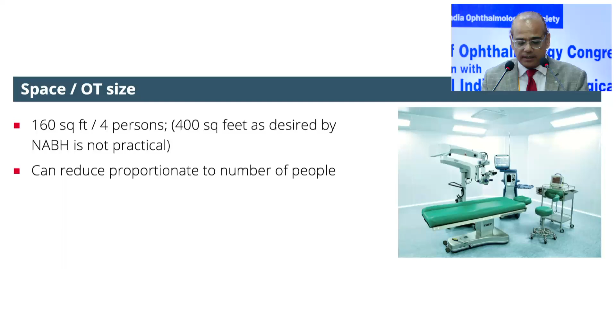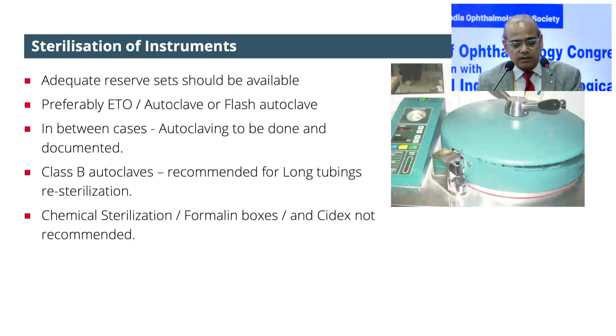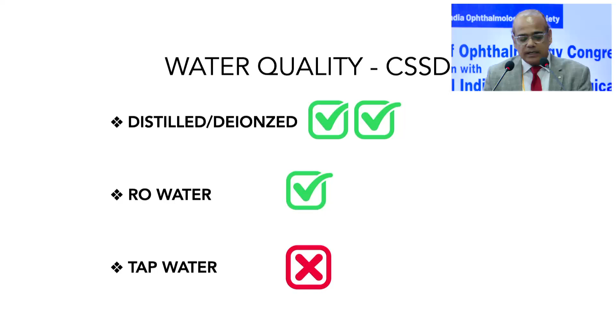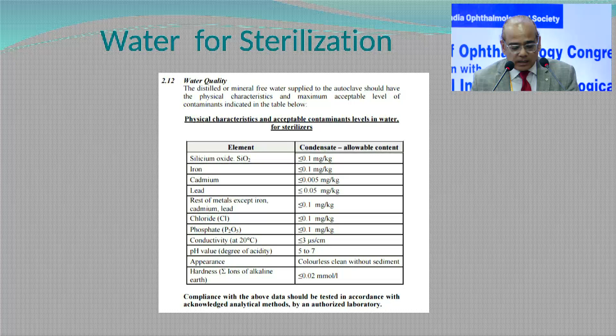Now coming to the sterilization of instruments. Adequate reserve sets need to be available, preferably ETO, autoclave or flash autoclave. In between cases, autoclaving is to be done and documented. A class B autoclave is recommended for long tubings and for re-sterilization. Chemical sterilization, formalin boxes and Cidex are not at all recommended. Water quality: it needs to be distilled or deionized. RO water will also do, but no tap water. These are the physical characteristics for the water we use, because in a recent outbreak this cluster of endophthalmitis occurred because of the water supply.